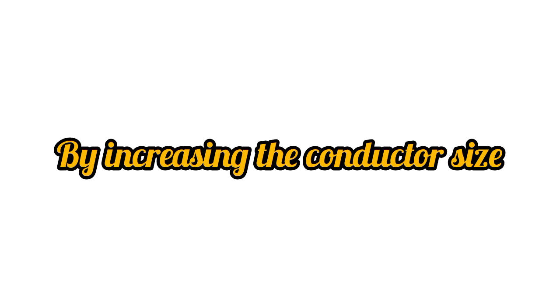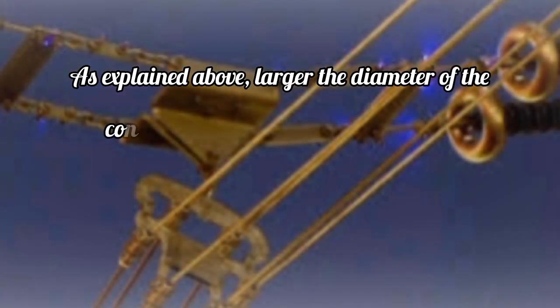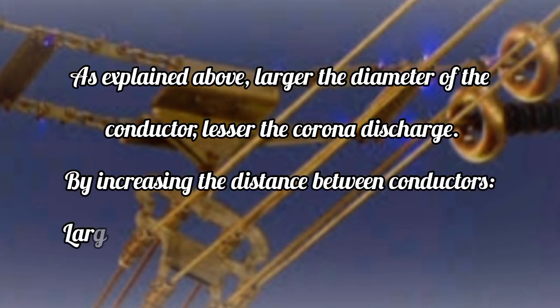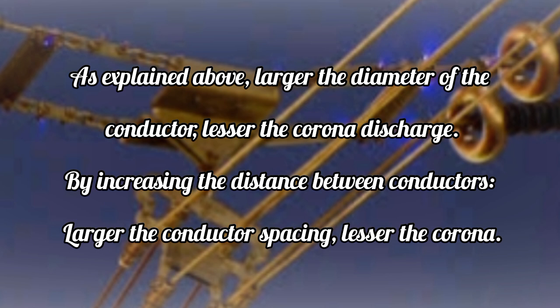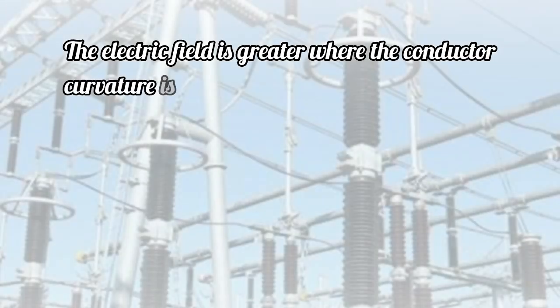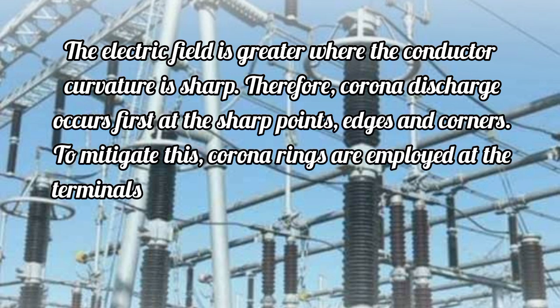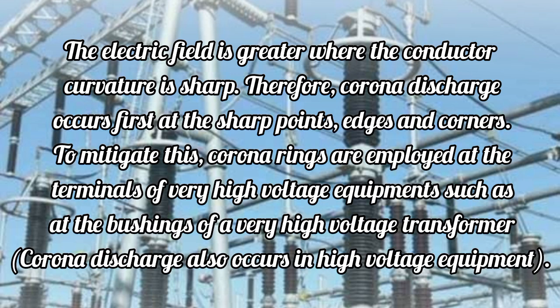By increasing the conductor size, as explained above, the larger the diameter of the conductor, the lesser the corona discharge. By increasing the distance between conductors, the larger the conductor spacing, the lesser the corona. Using corona rings: the electric field is greater where the conductor curvature is sharp. Therefore, corona discharge occurs first at the sharp points, edges and corners.